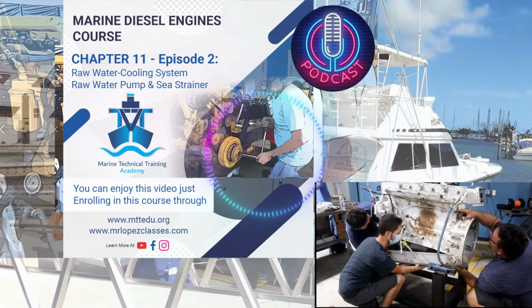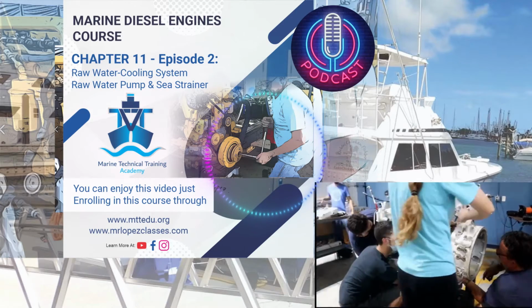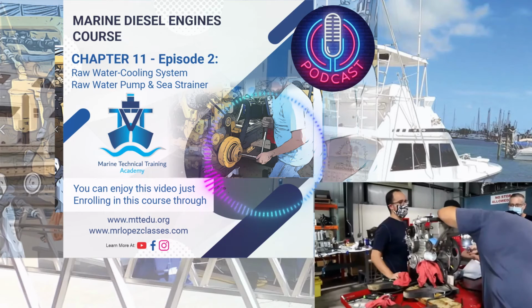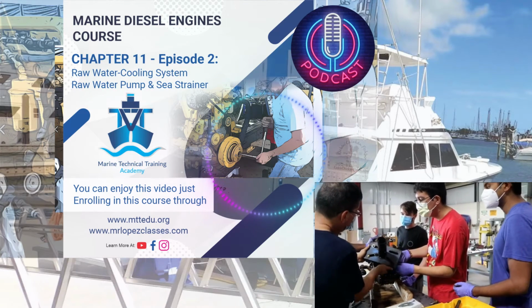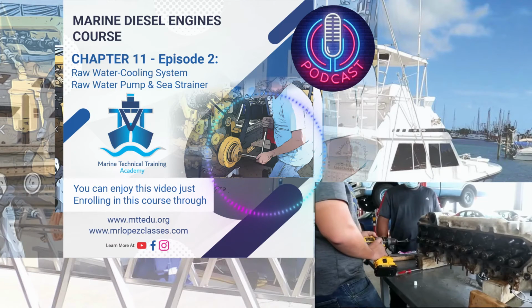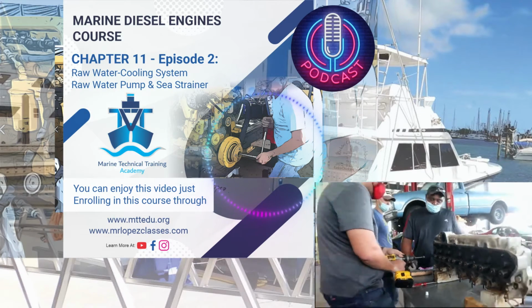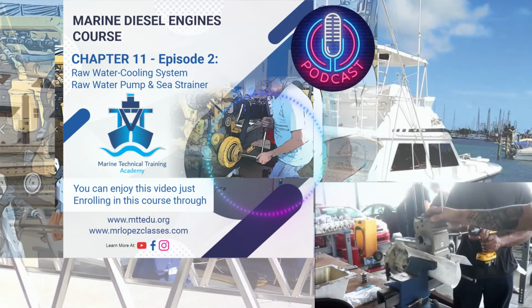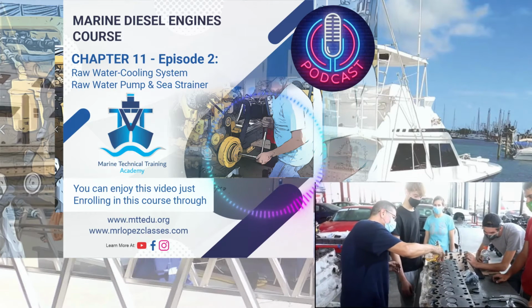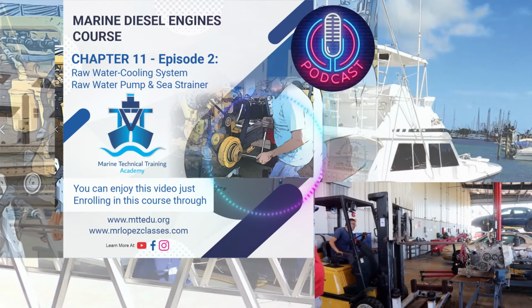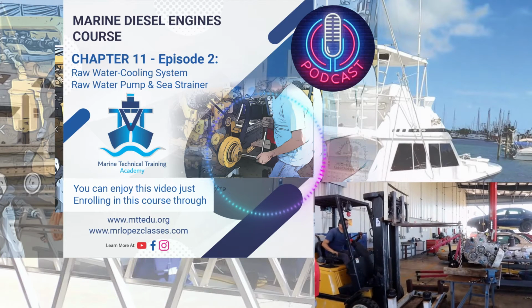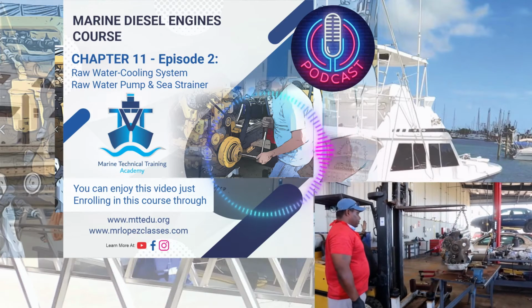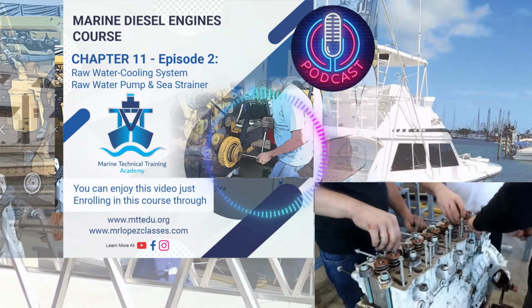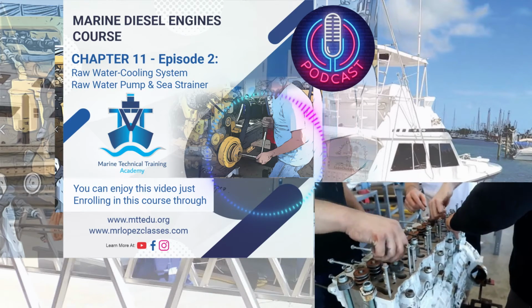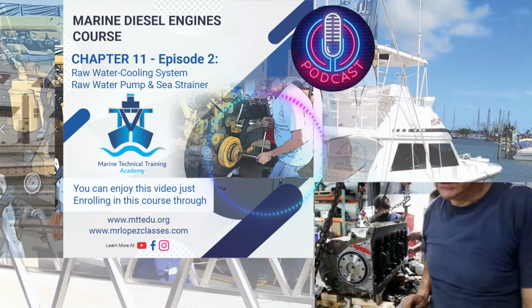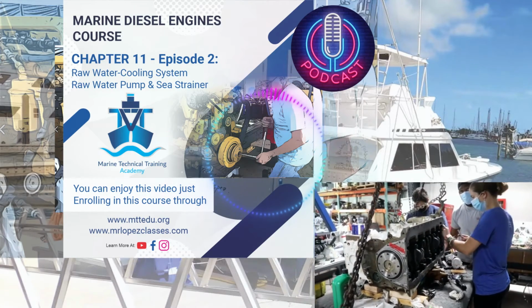We are going to close both ends properly. And now we are going to apply pressure in the middle in order to remove the impeller carefully. And right now we have the impeller. The impeller is ready to be replaced. Be careful when you remove the impeller. Be careful with the half moon.